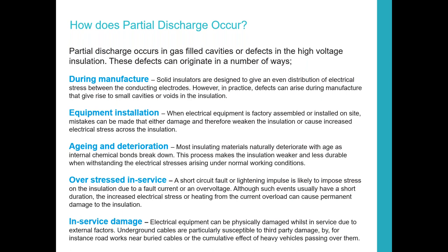Overstress in service. If an asset is exposed to currents, it gets stressed, thermal stress, can get some shock, and those stresses can lead to a breakdown in the insulation. And then in-service damage. If a cable is struck by something, or an insulated bus bar is damaged by something dropping on it, and that insulation layer is nicked or cut, that's going to be a probable location of partial discharge.